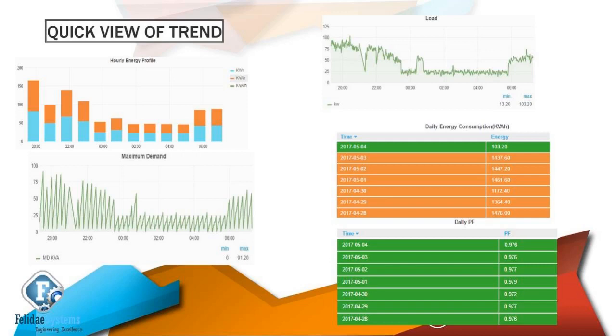2500 kVA means the distribution company says you can use up to that, but if you consume more, they will penalize you. Now, if your load suddenly shoots up to 2700 kVA, will you be penalized? No. What they do is accumulate readings every half an hour and take the average of that, and that is what is calculated as the maximum demand. Our system supports all these algorithms to calculate your maximum demand.